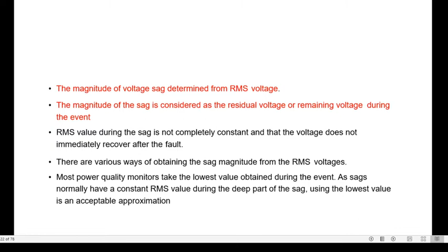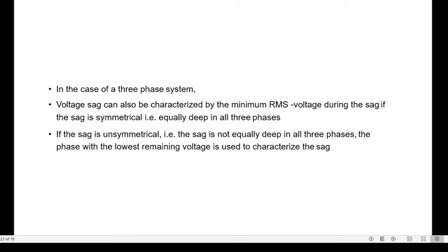Most power quality monitors take the lowest value obtained during the event, as sags normally have a constant RMS value during the deep part of the sag. Using the lowest value is an acceptable approximation. In the case of a three-phase system, the voltage sag can be characterized by the minimum RMS voltage during the sag if the sag is symmetrical, that is, equally deep in all three phases. If the sag is unsymmetrical, that is, not equally deep in all three phases, meaning it has different values in the RYB phases, the phase with the lowest remaining voltage is used as the reference value to define the characteristics of the sag in terms of the voltage sag magnitude.